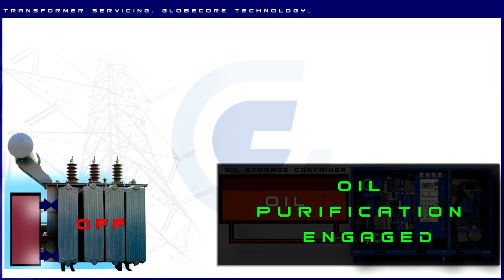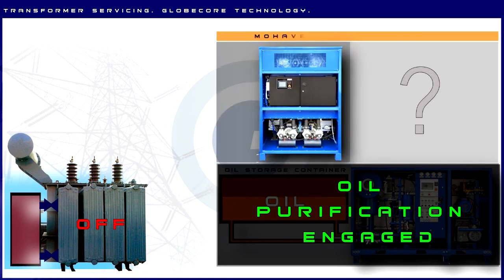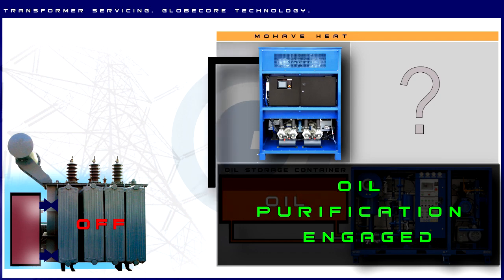While the oil is being purified, we connect the GlobeCore Mohave Heat unit to the transformer to protect its windings from moisture while the transformer is not airtight. Mohave Heat creates excess pressure in the transformer tank, preventing moist atmospheric air from entering.